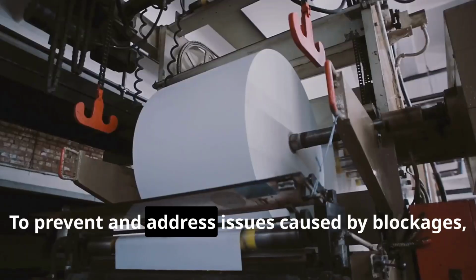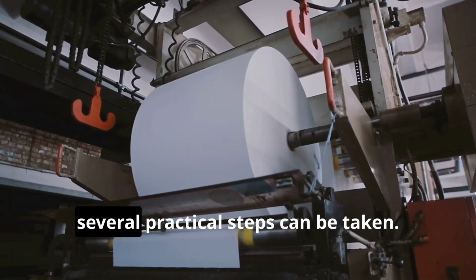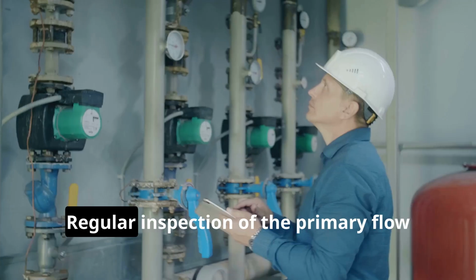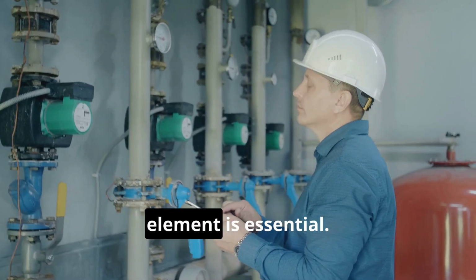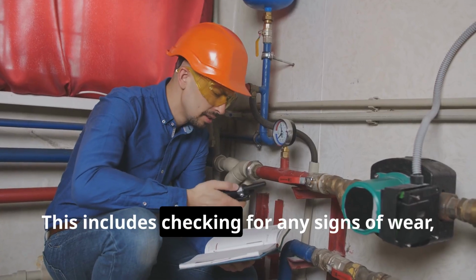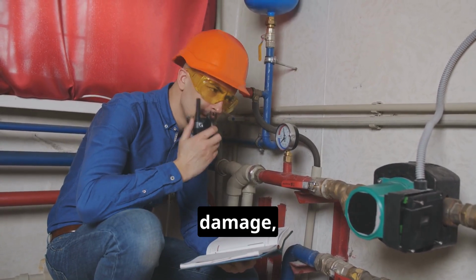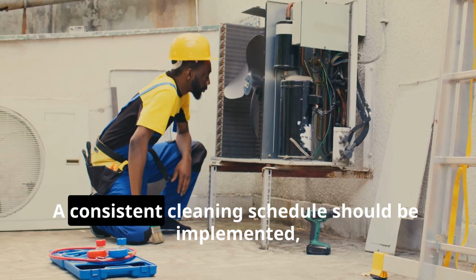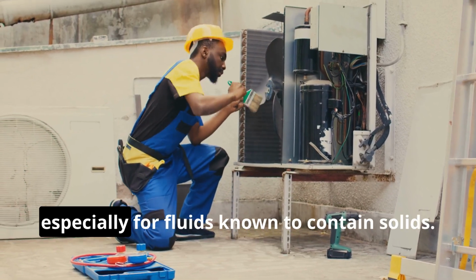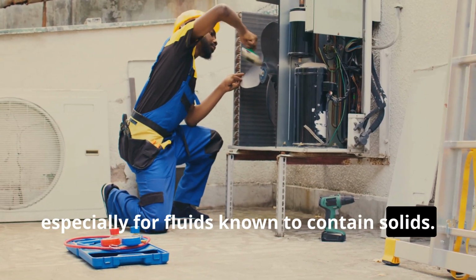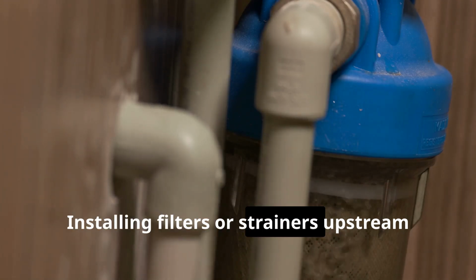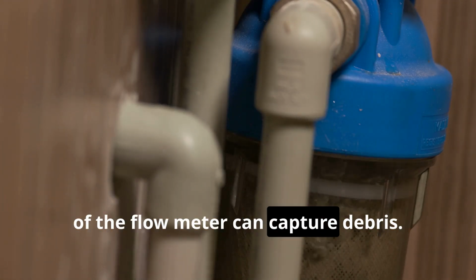To prevent and address issues caused by blockages, several practical steps can be taken. Regular inspection of the primary flow element is essential. This includes checking for any signs of wear, damage, or buildup. A consistent cleaning schedule should be implemented, especially for fluids known to contain solids. Installing filters or strainers upstream of the flow meter can capture debris.